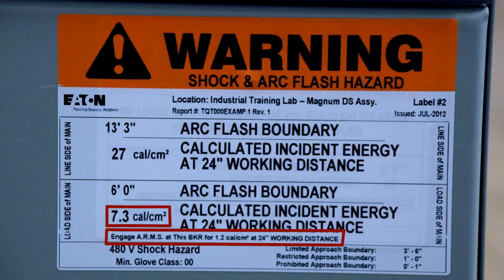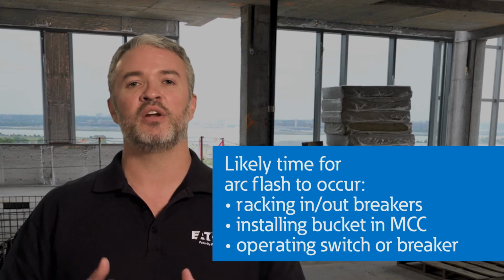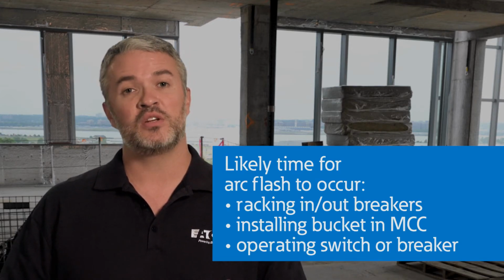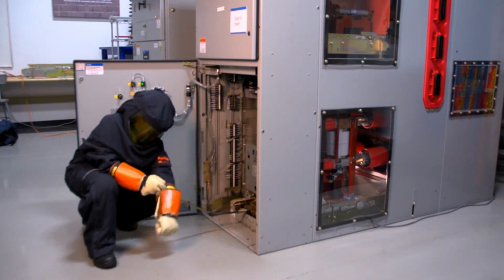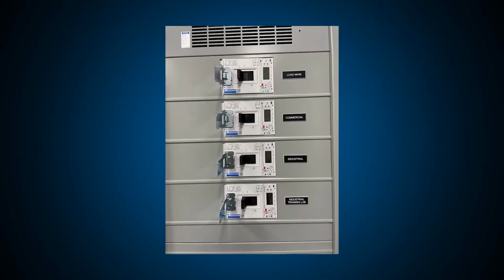The label may also indicate a secondary incident energy level and arc flash boundary if the arc flash reduction means are installed. The most likely time for an arc flash to occur is during interaction with electrical equipment. This can include racking in or out breakers, installing a bucket in an MCC, or operating a switch or breaker, for example. An arc flash hazard analysis or study provides insight into the safety of a hospital's electrical system. Through training and the implementation of suitable solutions, the probability of an arc flash event can be reduced, in some cases without investment in equipment or further studies.